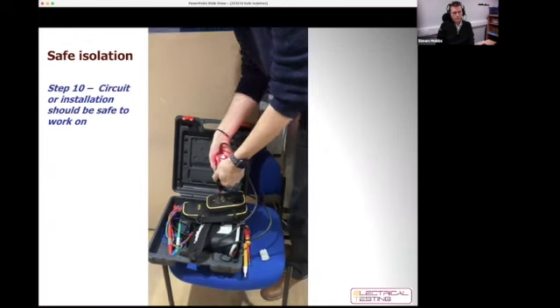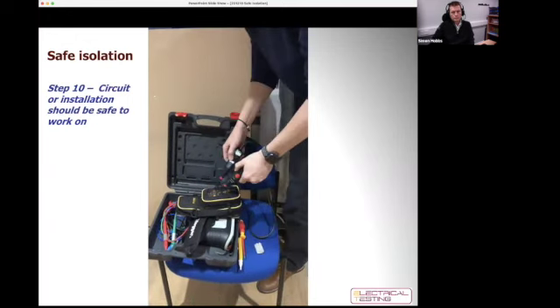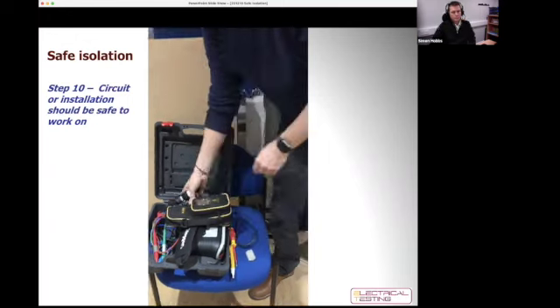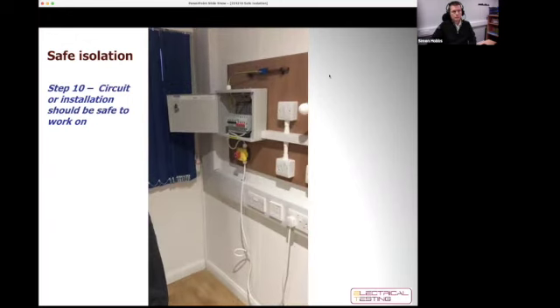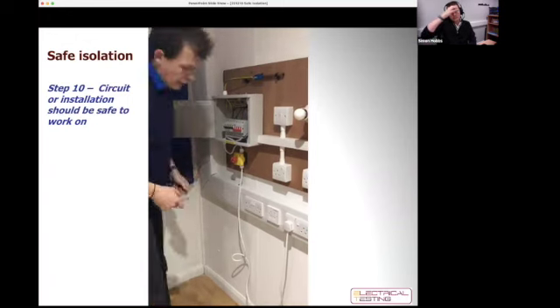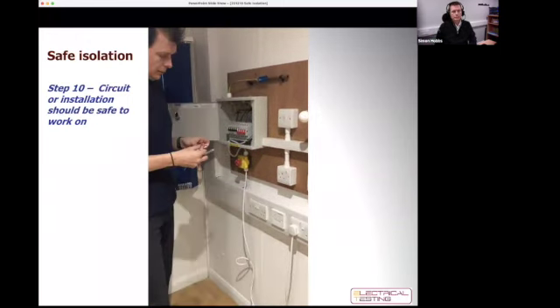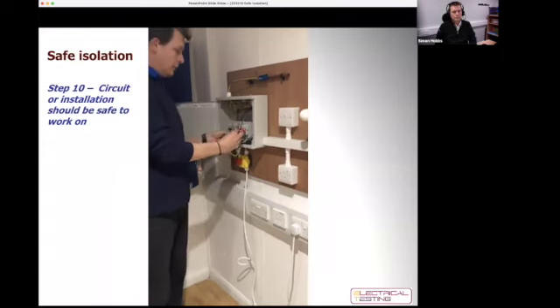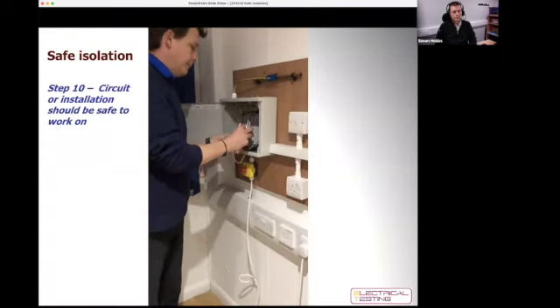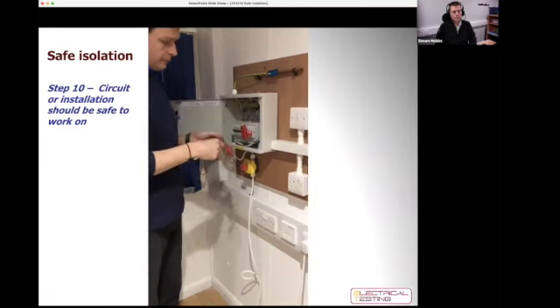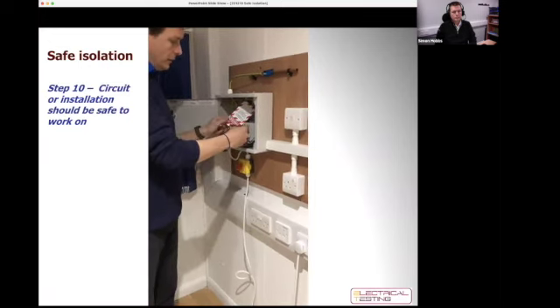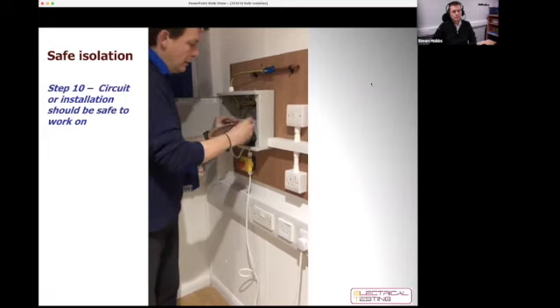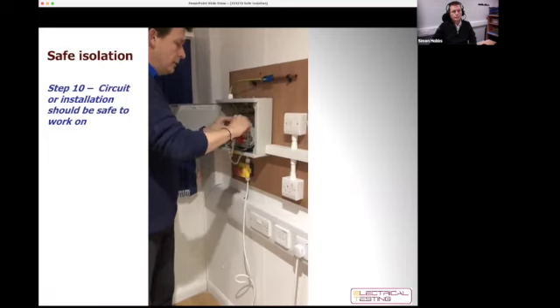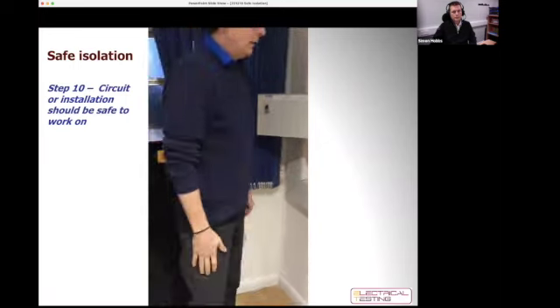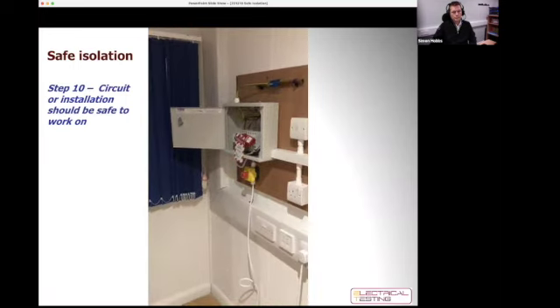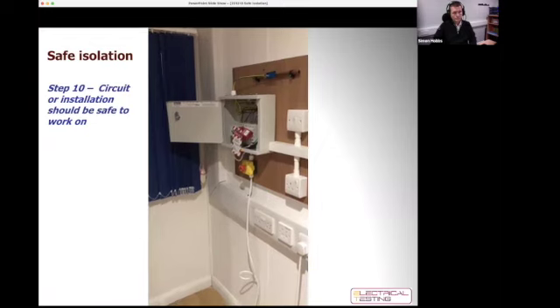Prove that my unit's still working. Why have you reproved that the unit's working? To check that it's still working and that I'm not getting any false positives or false negatives. Thank you. And before I carry on with any work, I'm now going to lock off and secure my isolation point with a lock off kit and a warning notice, like so. And I'm going to take the key and secure that in my pocket, and now I shall carry on my dead work. I'm happy that you've successfully completed the safe isolation process. Thank you, Simon.